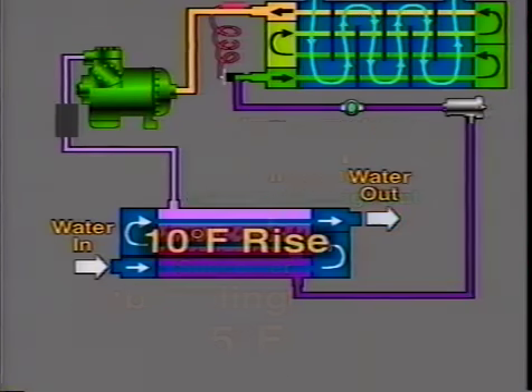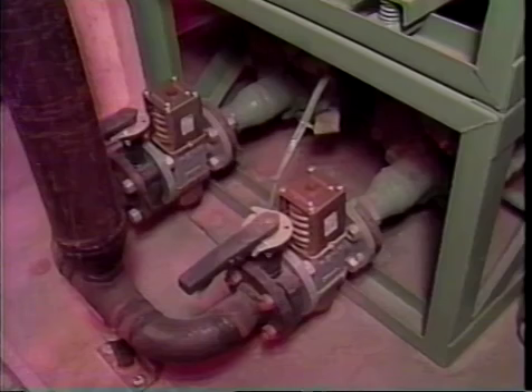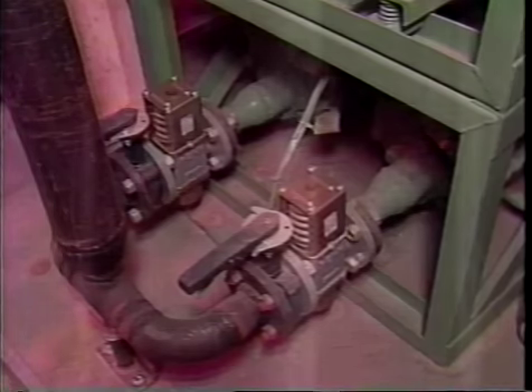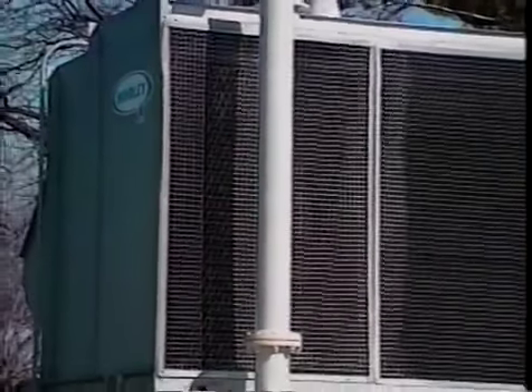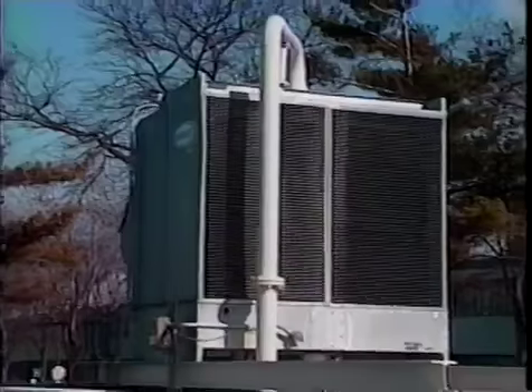Water leaving the condenser will generally have a 10-degree rise over the entering water temperature. The condenser water will typically be controlled by water regulating valves if it's a once-through system. These valves are installed in the entering or leaving water line and regulate the flow of water by sensing the condenser pressure. More commonly, however, the condenser water will recirculate through a cooling tower.